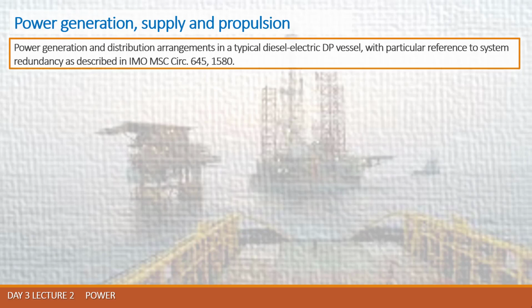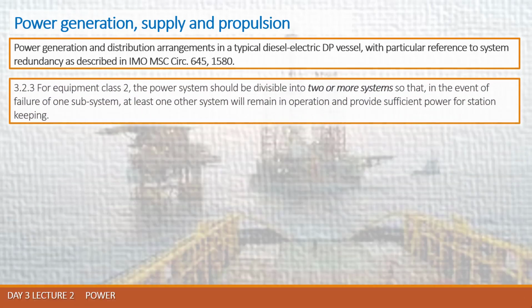The power systems may be run as one system during operation, but should be arranged by bus tie breaker. Remember this word: the breaker which separates two or more main supply buses between themselves. It should separate the system automatically upon failures which could be transferred from one system to another, including but not limited to overloading and short circuits.